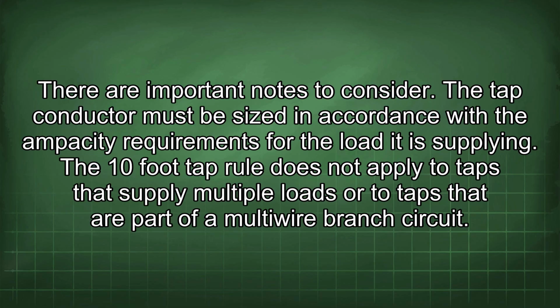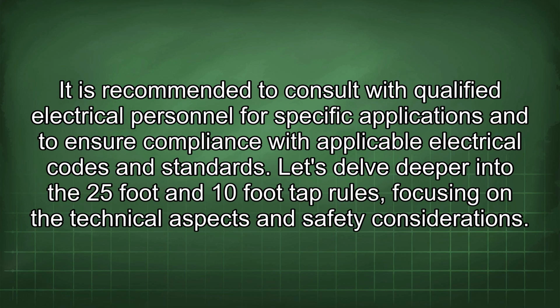There are important notes to consider. The tap conductor must be sized in accordance with the ampacity requirements for the load it is supplying. The 10-foot tap rule does not apply to taps that supply multiple loads or to taps that are part of a multi-wire branch circuit. It is recommended to consult with qualified electrical personnel for specific applications and to ensure compliance with applicable electrical codes and standards.